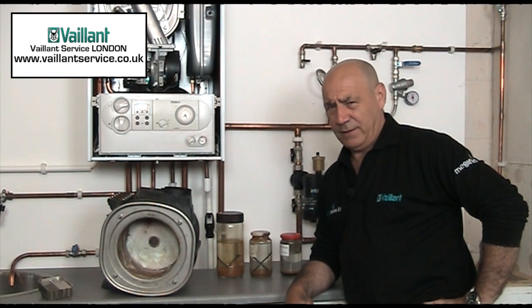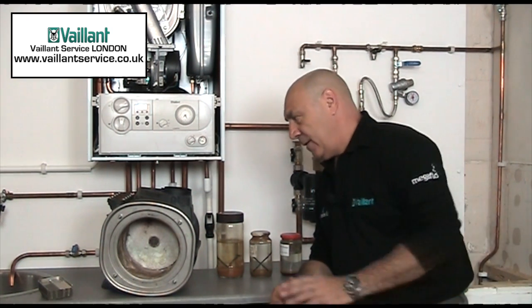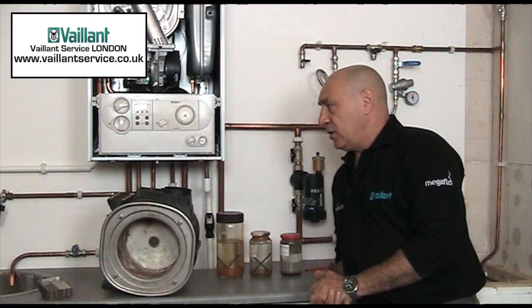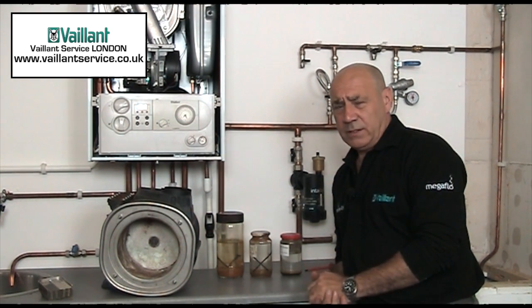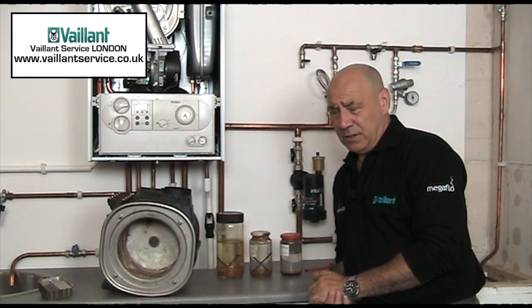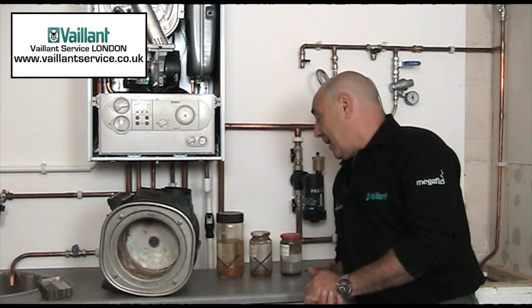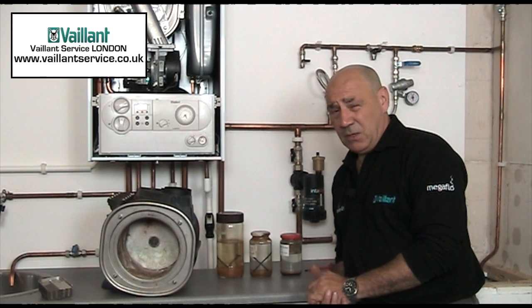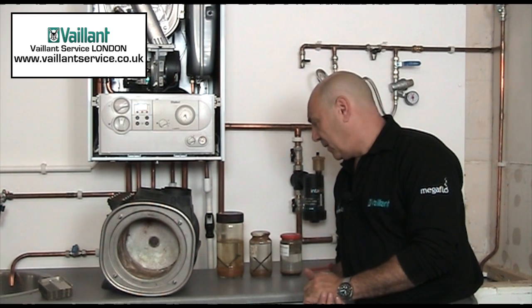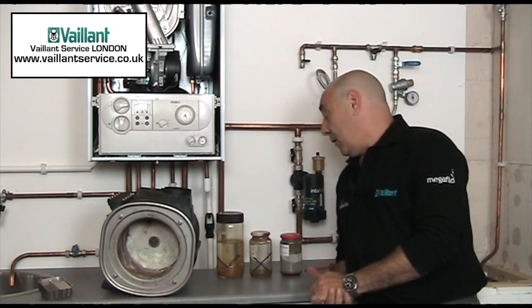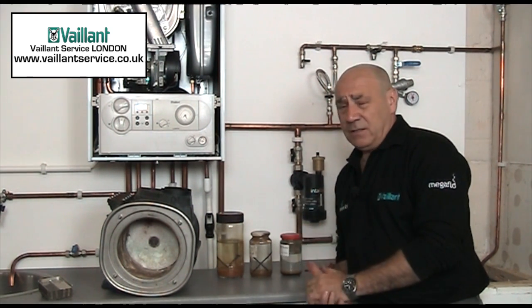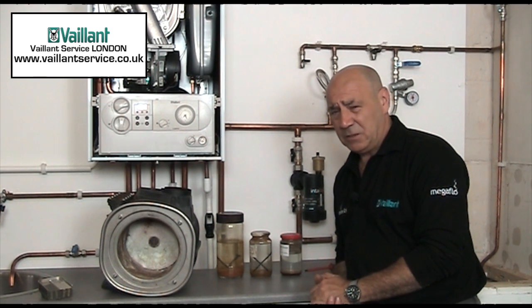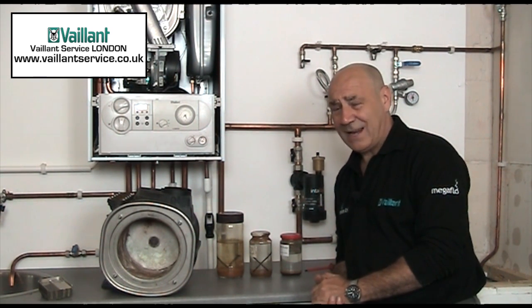This is going to be a quite long-winded series of videos about power flushing and system corrosion. This is a huge problem in the industry, especially concerning low water content boilers and in particular modern condensing boilers with the heat exchangers that they use. Power flushing is quite a laborious process — it's long and can be quite messy, but it is a necessary evil. Every heating system and modern condensing boiler requires it without a shadow of a doubt. Your heating system water needs to be as clean and as immaculate as possible, as close to drinking water quality as possible.